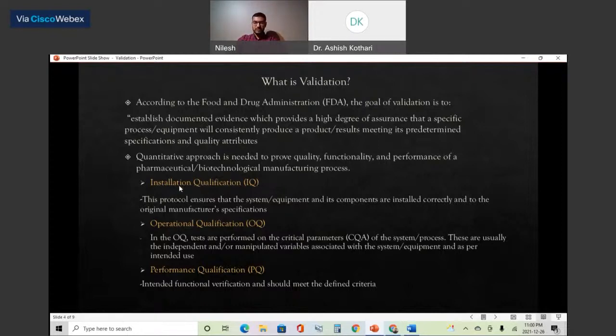So let's see installation qualification. In installation qualification, it is very simple. In IQ, you don't need to be worried. It should be installed as per the manufacturer's specification. If they say you should operate the machine at this speed, you have to operate at that speed, not more than that. Otherwise, there will be more maintenance and more and more breakdowns, and you cannot run the machine consistently.